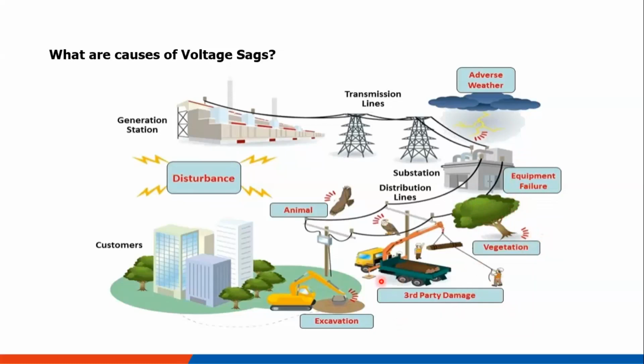Third-party damage, such as people working near the lines, can cause voltage sag. Animal encroachment, an animal standing next to a bare conductor, can cause a short circuit, which then causes a voltage sag. Excavation, where people excavate to lay fiber, lay new cables, or do road works and then hit the cable, can cause voltage sag. Sometimes customers also cause voltage sag internally that will affect everyone. Okay, so these are some of the causes of voltage sags.